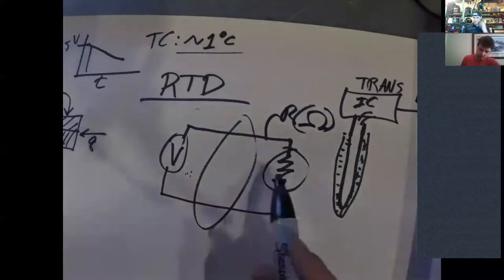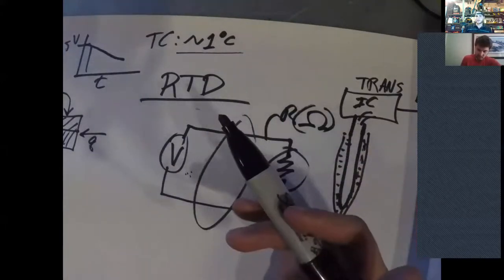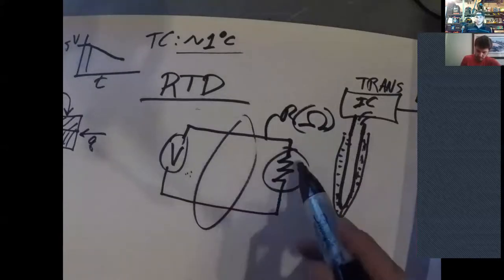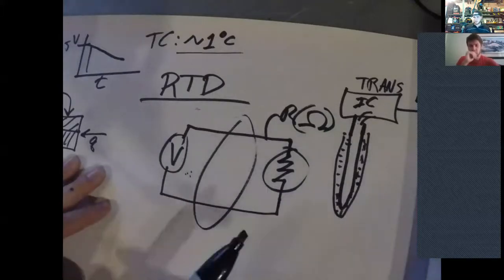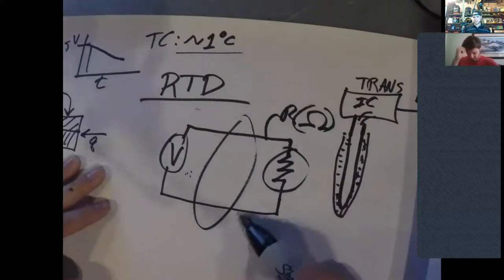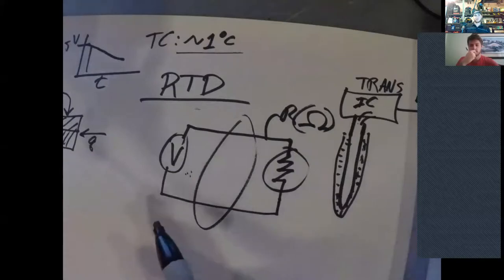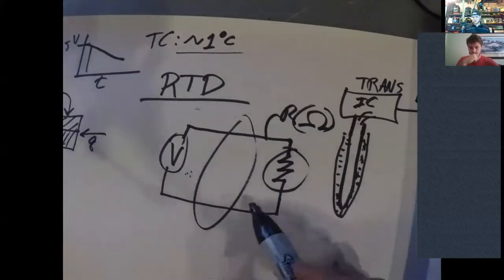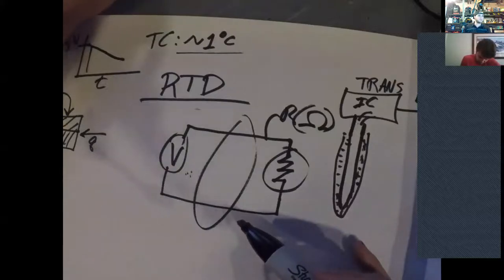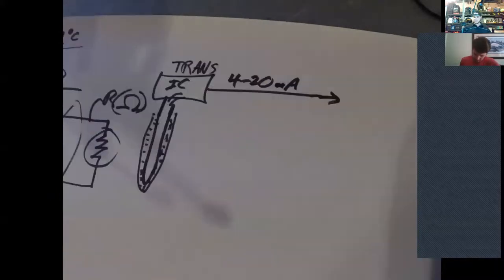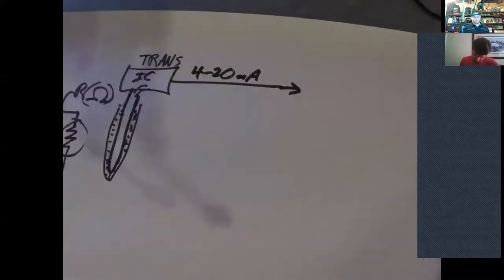Now over here, I showed you, this is a two wire RTD. And so you have your wires running back to your controller and these can be really long. Like, you know, you could have a hundred feet or more of wire. Does anybody see a problem with this setup?